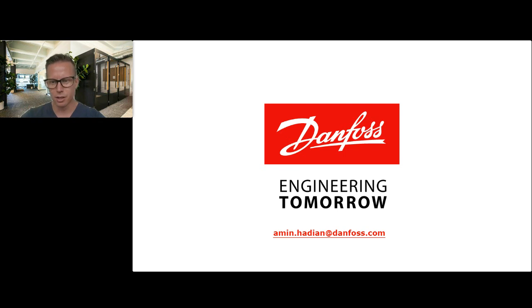Right. Then there is a question about whether this system of high pressure water mist requires an annual test to avoid any obstruction from inactivity? And as the water requires additional chemicals for maintenance, maybe you can say something about the regular tests of the pump itself that we require as component seller.